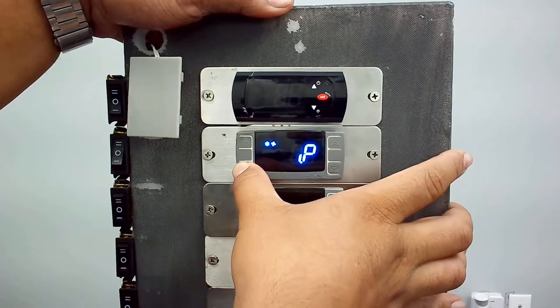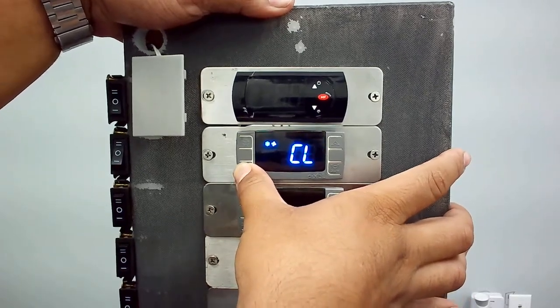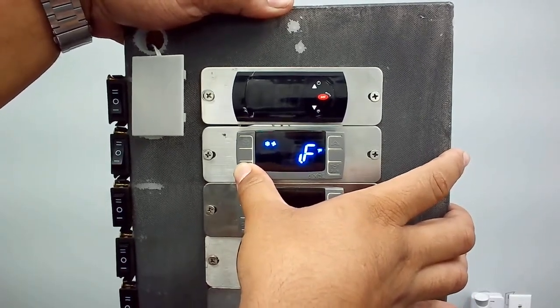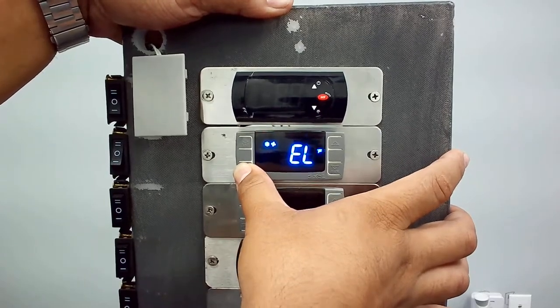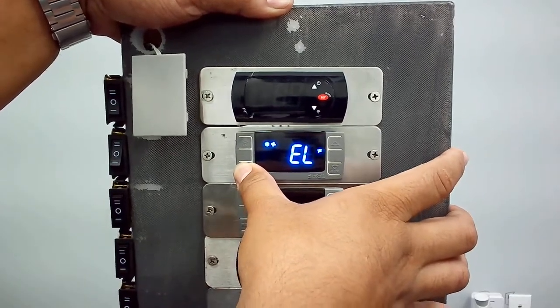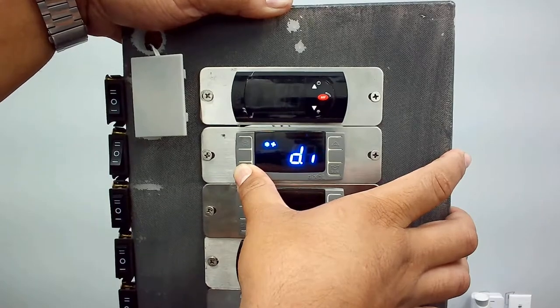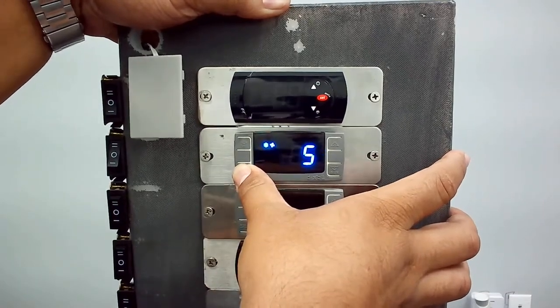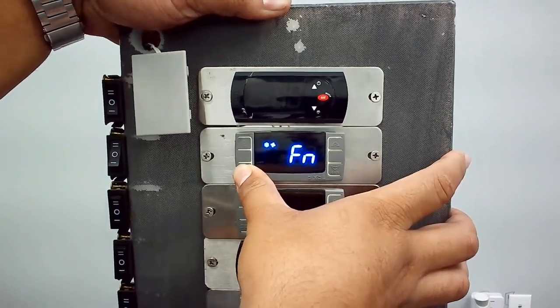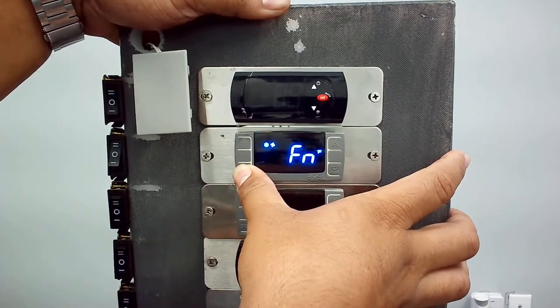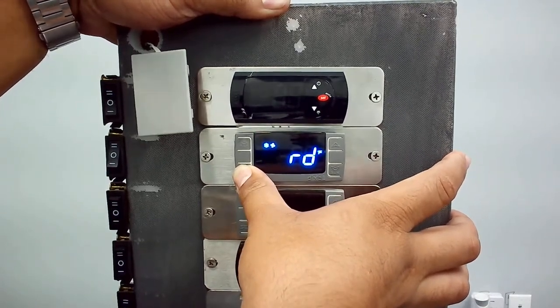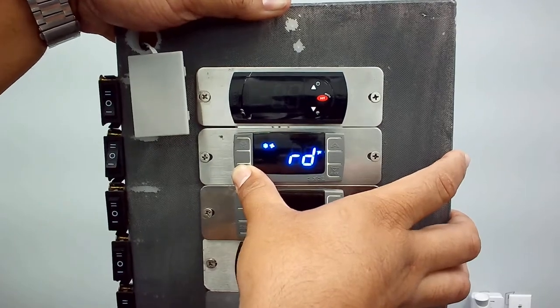IP, this is going to be for your doors, should be at CL. IF, once again, it's for the doors, should be at EL. This is for the actual alarm for it. DI should be set to 5. DC should be set to FN, regardless of units. And last but not least, RD should be set to Y.